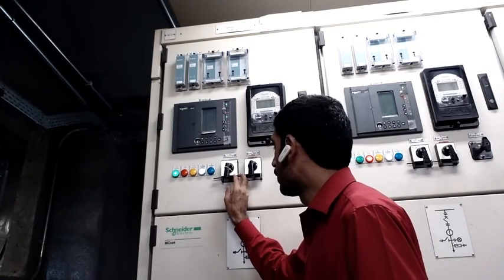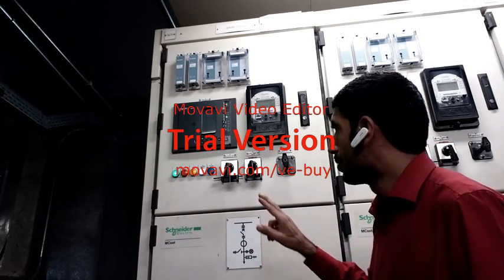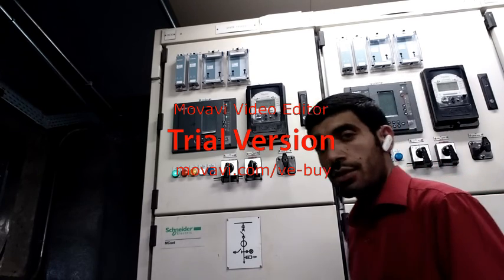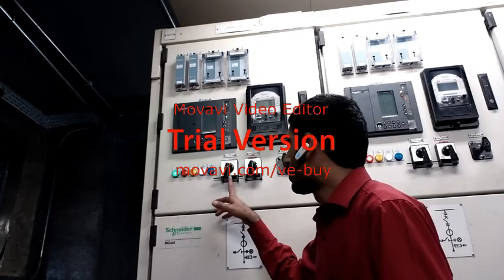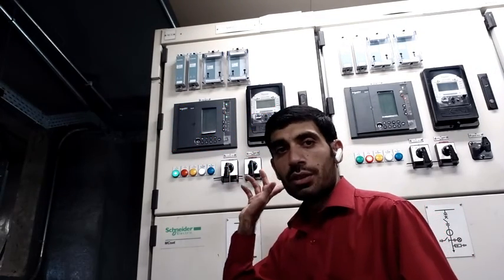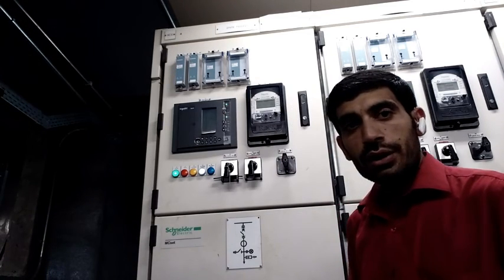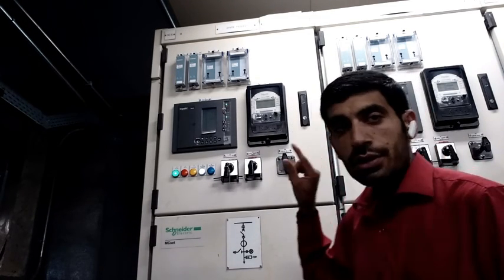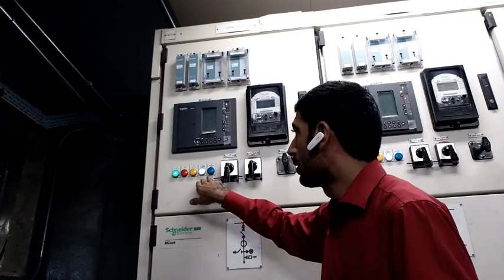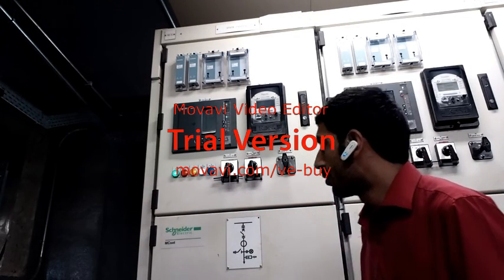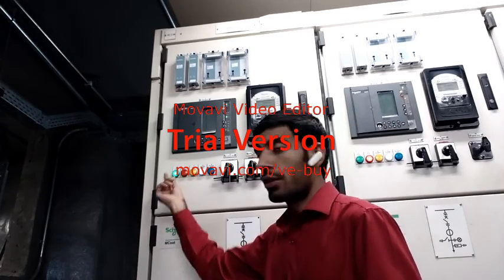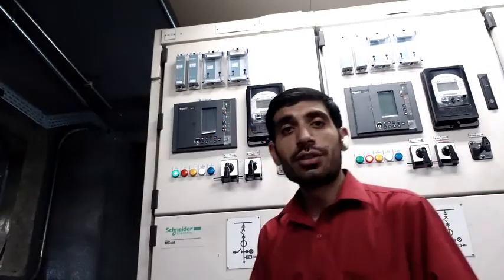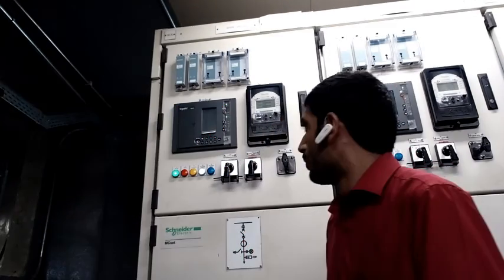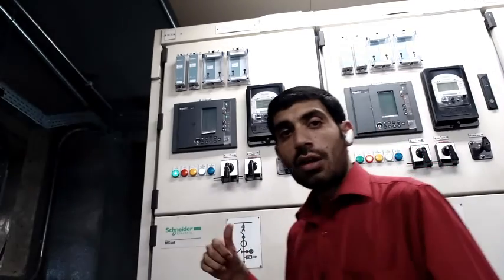And the next thing is this control switch. It has two positions, one is closed and one is tripped. This is used for the breaker. If we want to close, we put it in the closed condition, and if we want to trip our breaker, we put it on the trip condition. There are 4 or 5 indicators used for different conditions. The green indicator is used for breaker normally open, red indication for breaker closed, yellow indication for tripping, and white indication shows the charging of the breaker.